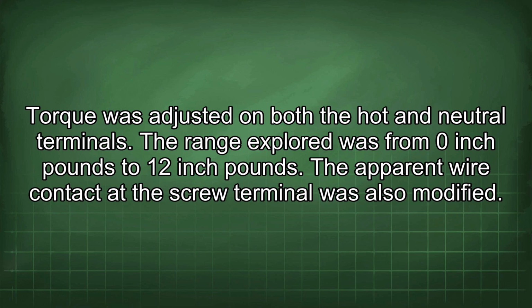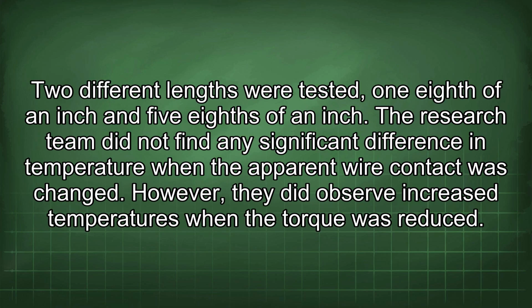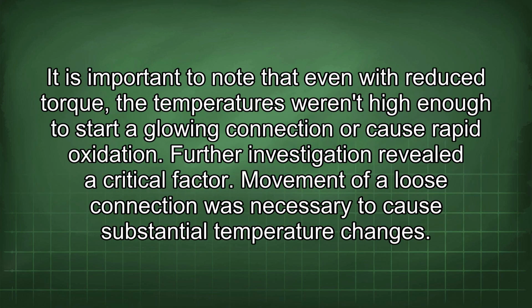The apparent wire contact at the screw terminal was also modified. Two different lengths were tested, 1/8 of an inch and 5/8 of an inch. The research team did not find any significant difference in temperature when the apparent wire contact was changed. However, they did observe increased temperatures when the torque was reduced.